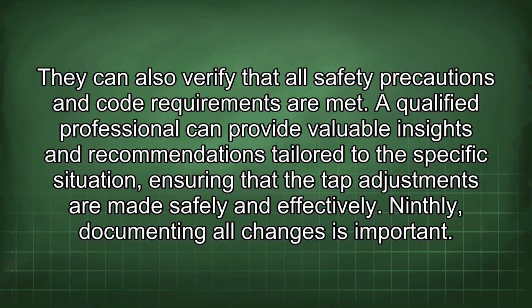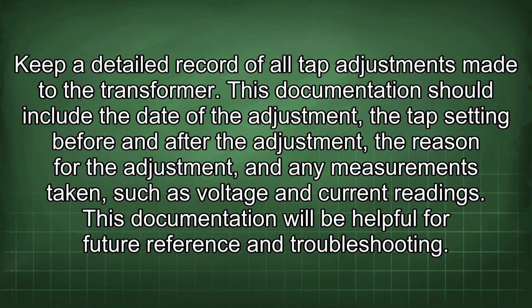A qualified professional can provide valuable insights and recommendations tailored to the specific situation, ensuring that the tap adjustments are made safely and effectively. Ninthly, documenting all changes is important. Keep a detailed record of all tap adjustments made to the transformer. This documentation should include the date of the adjustment, the tap setting before and after the adjustment, the reason for the adjustment, and any measurements taken, such as voltage and current readings. This documentation will be helpful for future reference and troubleshooting.